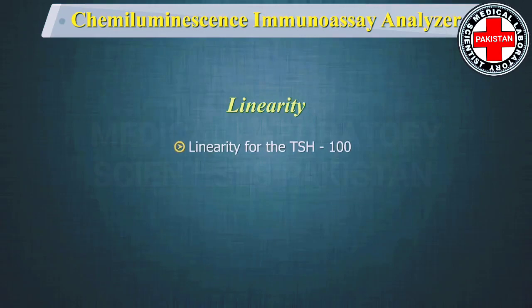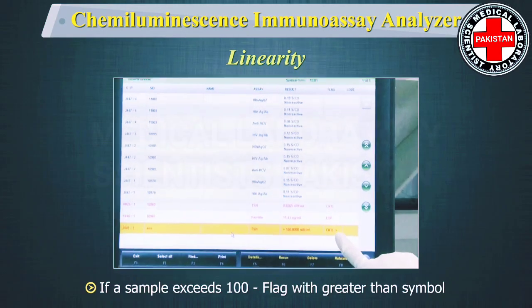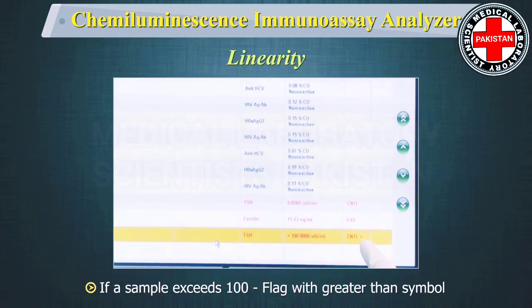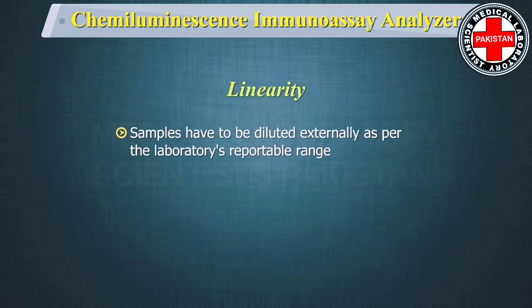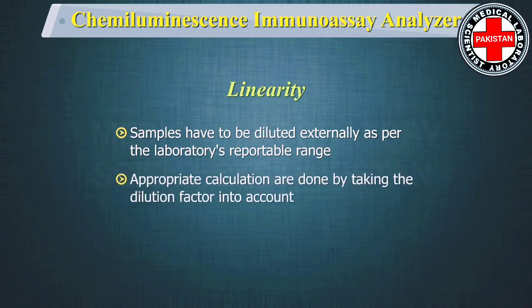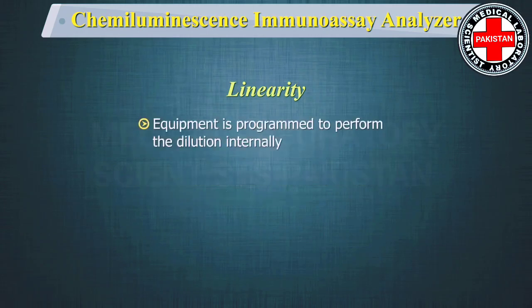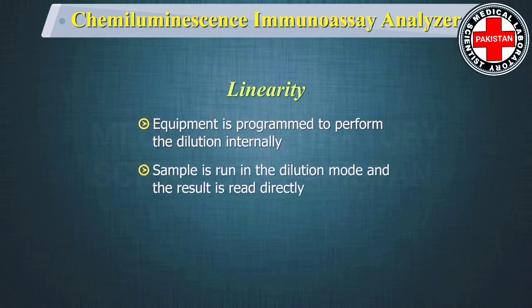Linearity for TSH is 100. If a sample exceeds 100, it will flag with the greater-than symbol. In many analyzers, samples have to be diluted externally as per the laboratory's reportable range, with appropriate calculation taking the dilution factor into account. The equipment used in this demonstration can be programmed to perform the dilution internally, so the sample is run in dilution mode and the result can be read directly.